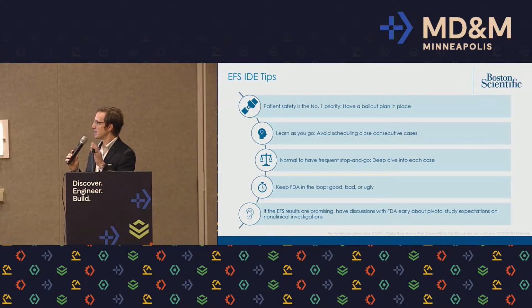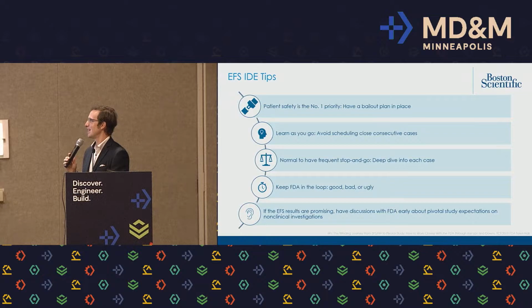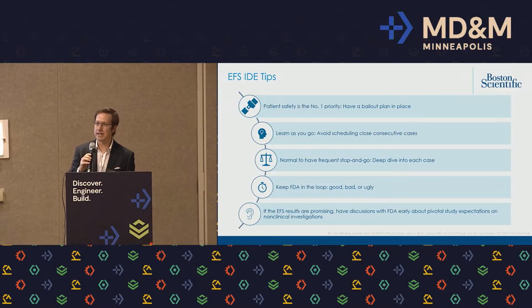It's normal to have this frequent stop and go and deep dive into each case as you learn. Keep FDA in the loop, the good, the bad, or ugly. And then if EFS results are promising, so if you get to the end of the 15 patients and everything looks good, have discussions with them about what that transition looks like to a pivotal IDE. Have that discussion early about what evidence they're going to need to support enrolling additional patients, because sometimes that might include a chronic animal study or more longer term critical path durability testing on the bench or something. And to get that started early can be an advantage to transition into your pivotal.